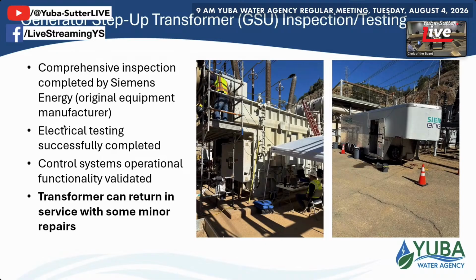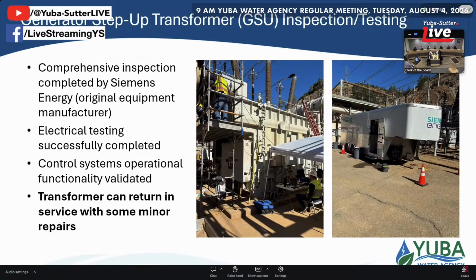This is called a GSU, generator step-up transformer. Both of our units are 13.8 kilovolt generators. That's the voltage they output, and we cannot change it because of the physical limitations of the size of the generators, RPMs, and that kind of stuff. The line we're attached to is a 230 kV transmission line accessible to us at the Yuba Water at Colgate powerhouse. So to bring the 13.8 up to 230 kV, we need equipment. This equipment helps us step up from 13.8 to 230 kV, and it's the most critical equipment in any power generation facility, anywhere, of any kind.